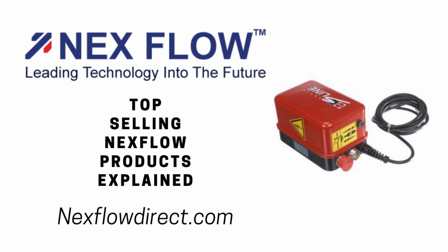You are dealing with high voltage power supplies. It can be a little bit tricky if you accidentally remove or attach a static bar, static point, or any sort of static elimination device to a high voltage power supply. So the safety connection is a big advantage.